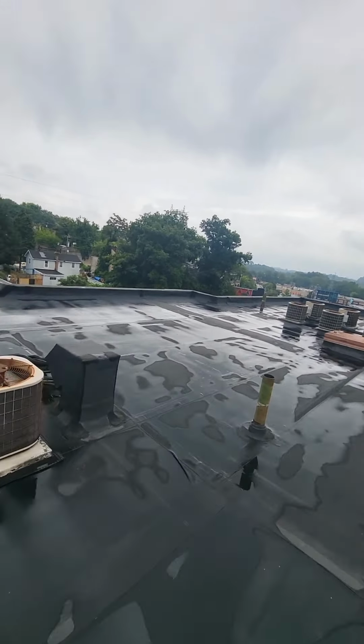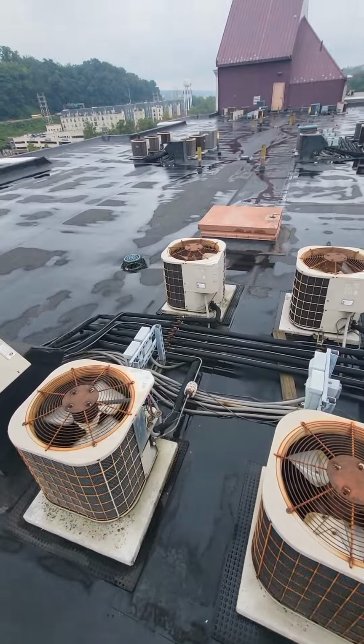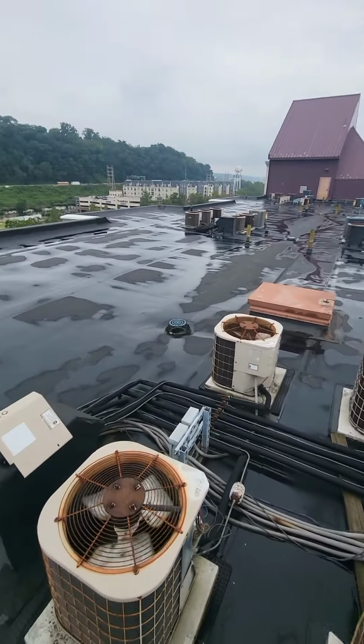So, and I looked at the thermostat wires, guys. The thermostat wires were still in good shape, but we popped in a new contactor and still the same thing. And guys, like I said, this didn't take much time. It's really, after a while, guys, of troubleshooting low voltage things, it can only be a handful of things. But a new contactor didn't work. The issue was the circuit board.